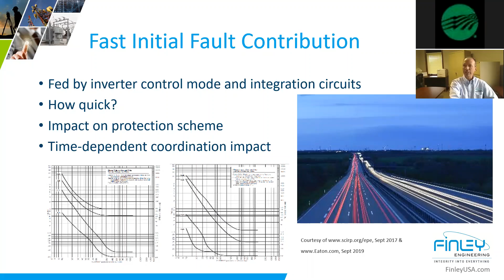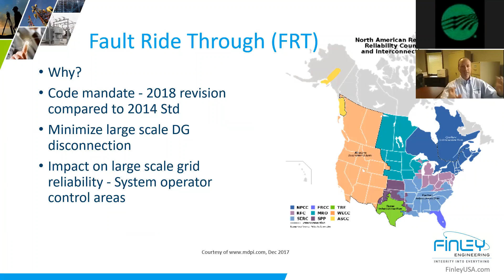Okay, the fault - right, so let's talk about that point, because this is important. I'm bringing that point back to a head that you were bringing up. So if this helps, look at what the reliability councils are doing. Ultimately, what I alluded to earlier is the point: yes, we know we've got to protect against faults, but we're looking at large scale reliability. The system operators for those control areas can't have multiple 2 to 10 megawatt systems coming offline at the same time. And if they're all built with similar electronic schemes, then potentially they could all be tripping together. That's why they've been designed to handle what grid operators would call minimum level threshold events - hang on, so to speak, so that they stay connected and they don't cause a cascade effect. That's really the point.